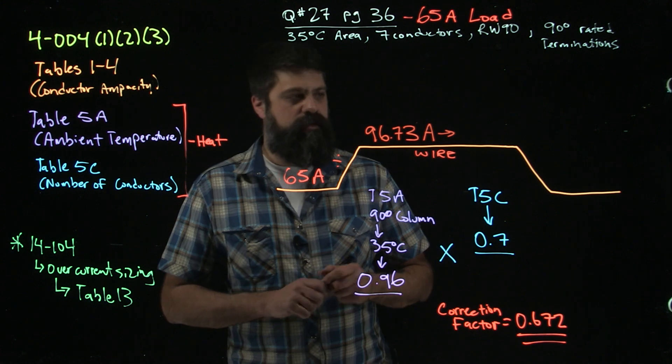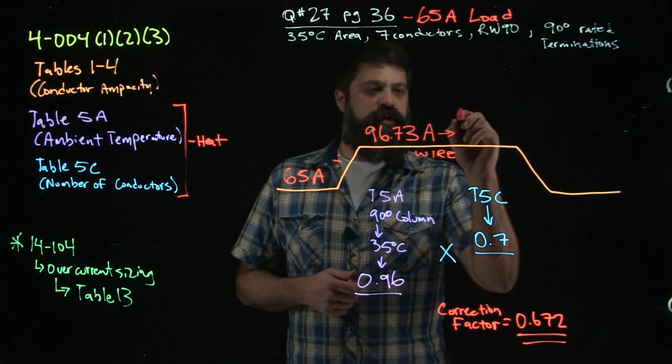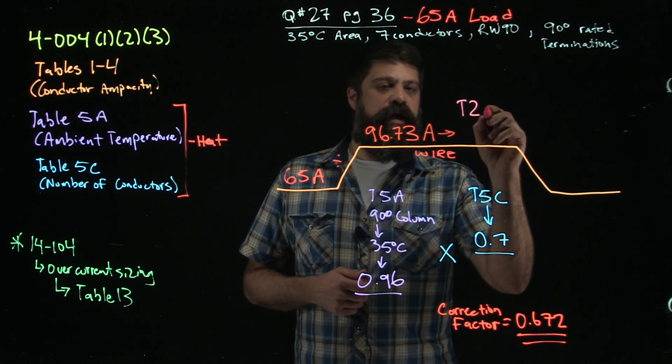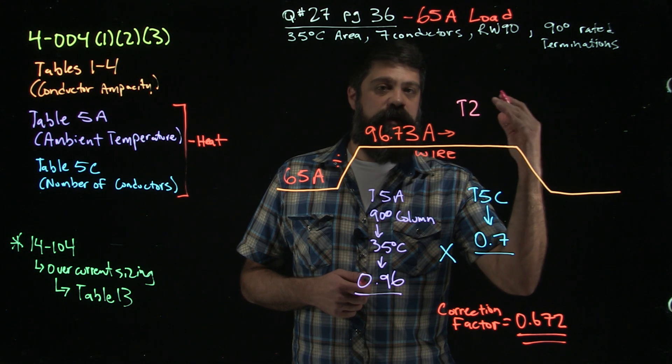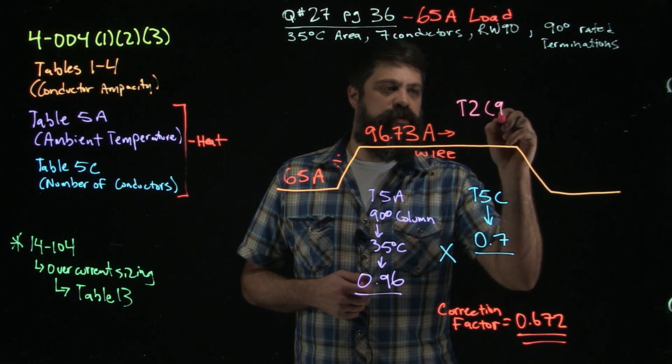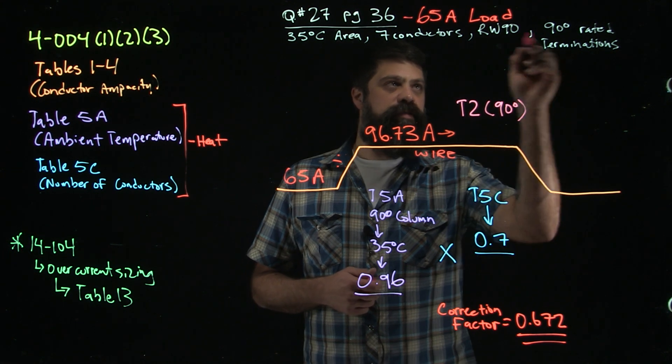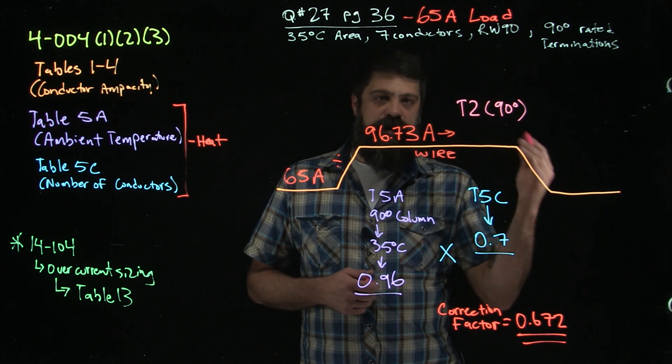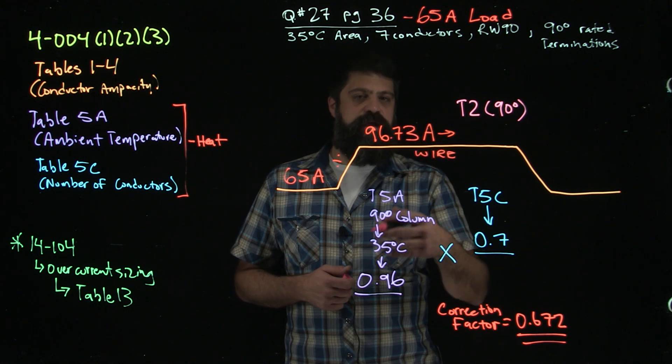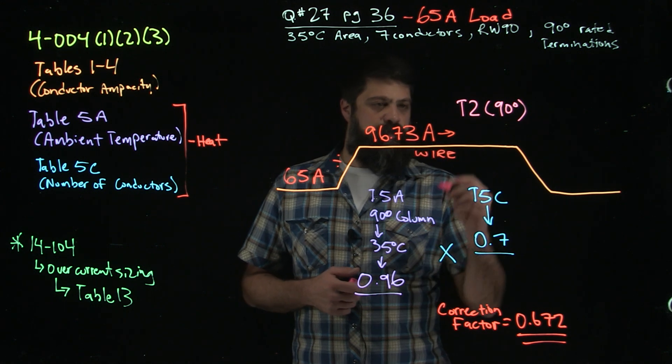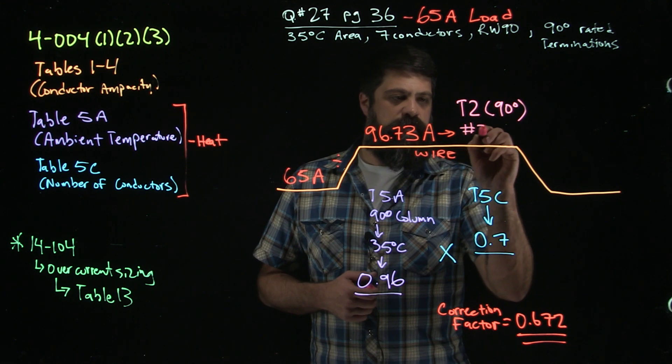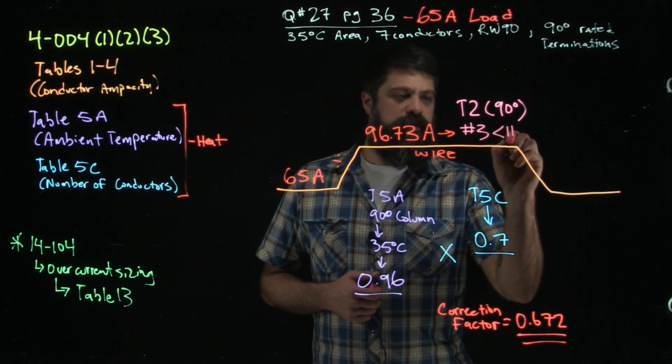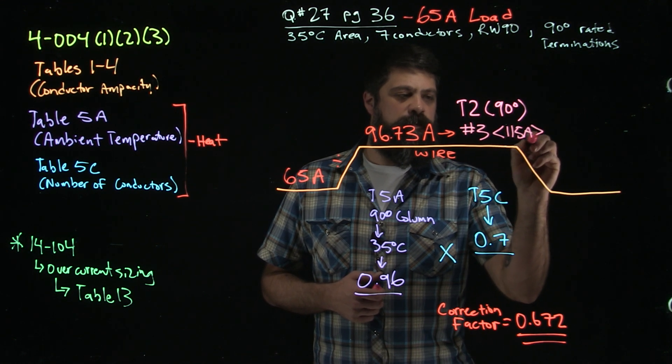If I take 96.73 amps, now I'm going to take that to Table 2 again. We're still dealing with copper conductors, and now instead of looking in the 75 degree column like we have been, we're going to move over to the 90 degree column. Everything's rated for 90 degrees, means it can handle more heat. So Table 2, the 90 degree column, if I look for something that's 96.73 amps or bigger, the next one up is the number 3, which is good for 115 amps.